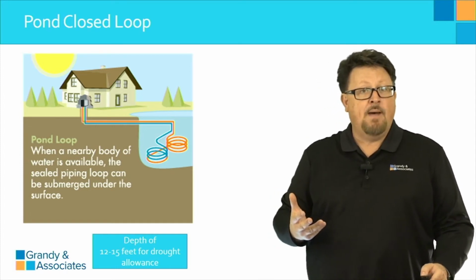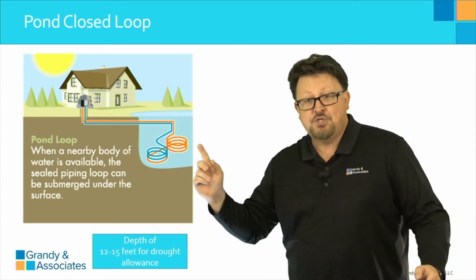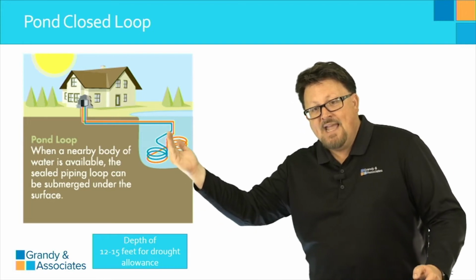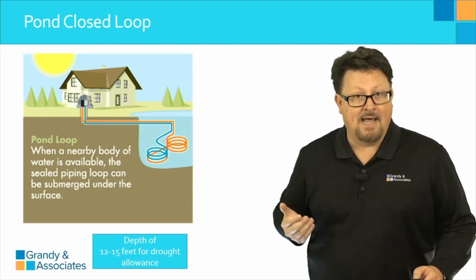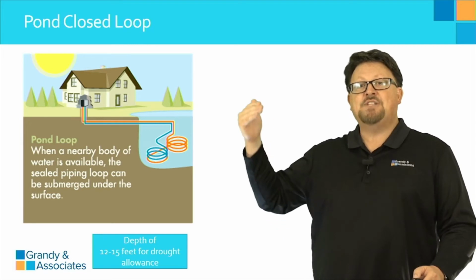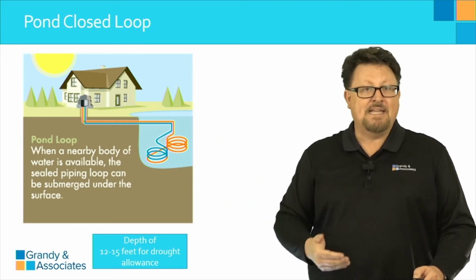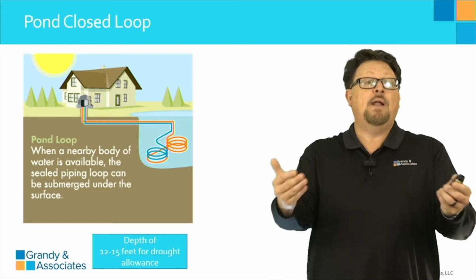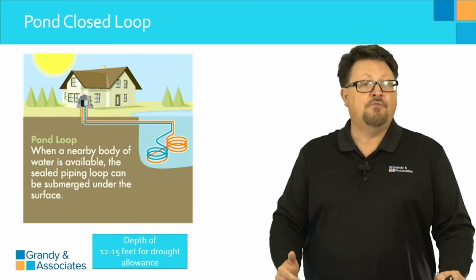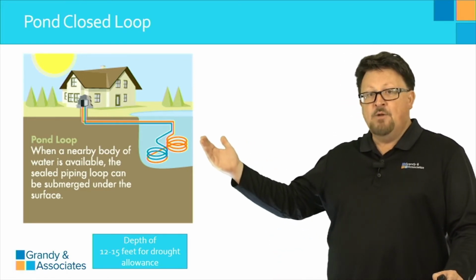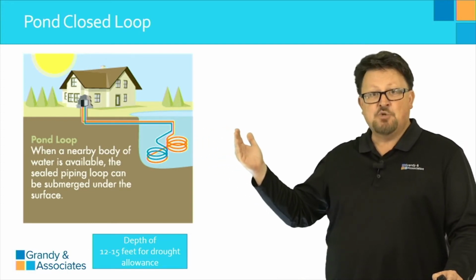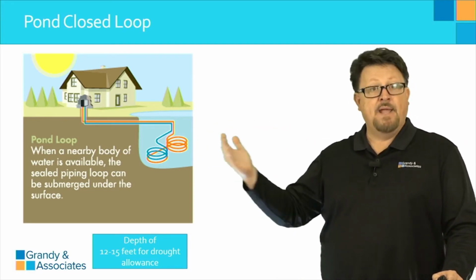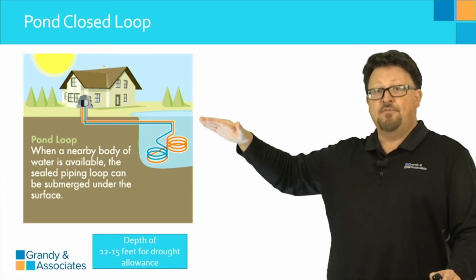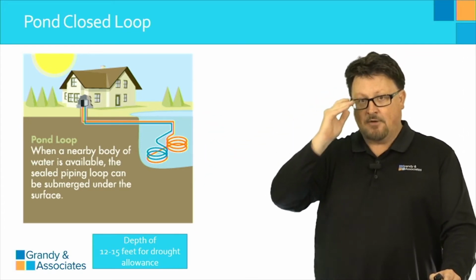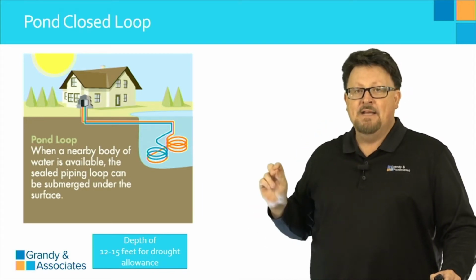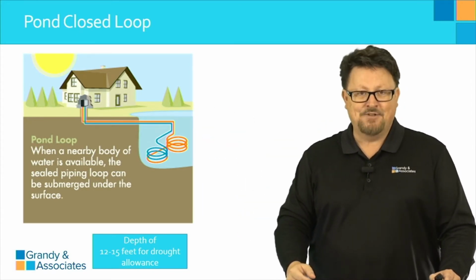One very important thing to keep in mind: you want to make sure this grid is far enough off the shoreline to account for drought cycles. Again, your local Corps of Engineers can give you guidance on what that looks like in your area, because it can be very different market to market. That may be anywhere from 10 to 12 feet, 15 to 20 feet, 30 feet or more, depending on where you live, as lake levels will vary as you go through drought cycles. So that's one very important thing to keep in mind with this loop design style.